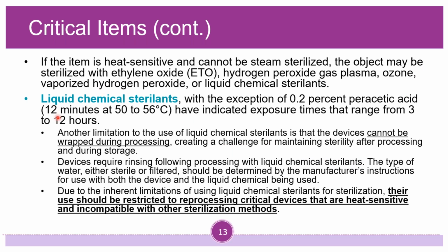Another thing that you need to know for liquid chemical sterilants are going to be some of your limitations. And that's what they're going to ask you on the test. What are your limitations with liquid chemical sterilants? Another limitation to the use of liquid chemical sterilants is that the device cannot be wrapped during processing, creating a challenge for maintaining sterility after processing and during storage. Devices require rinsing following processing with liquid chemical sterilants. The type of water, either sterile or filtered, should be determined by the manufacturer's instructions for use with both the device and the liquid chemical being used.